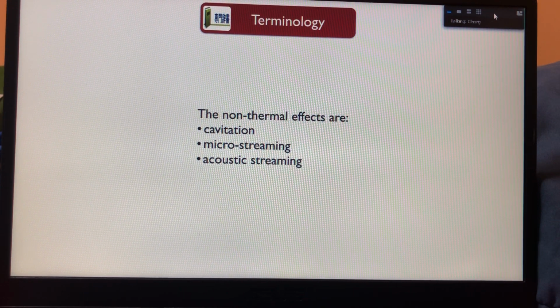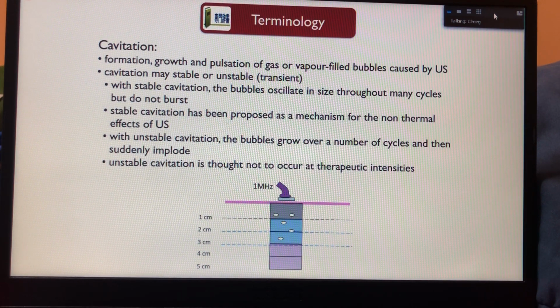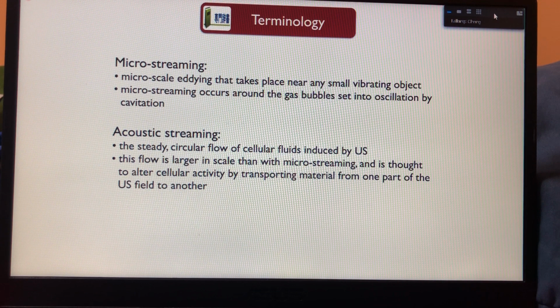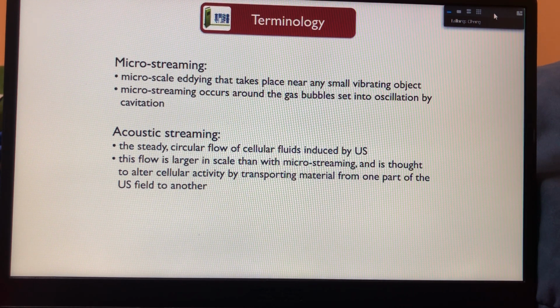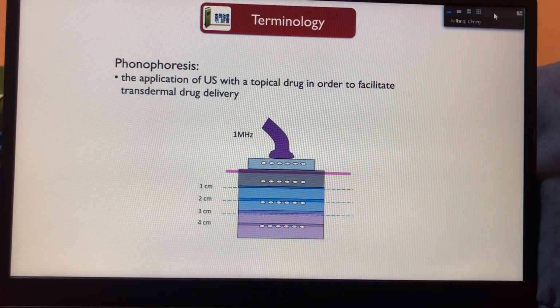But in the 60s and the 70s, they could go as high as 20 or even higher than that. And therefore, under those circumstances, yes, you get cavitation, microstreaming, acoustic streaming. But you have no way of having these effects in current devices. And in fact, these are actually red herrings. They're not really that important in therapeutic ultrasound. The main effect for therapeutic ultrasound is the thermal effect. And there is no such thing as non-thermal. Even at 0.1 watts per cm squared, that's still thermal. When you want to talk about non-thermal, then we talk about low intensity pulse ultrasound or LIPUS. That's non-thermal. But that has a totally different application from therapeutic ultrasound. So let's not come back to that.